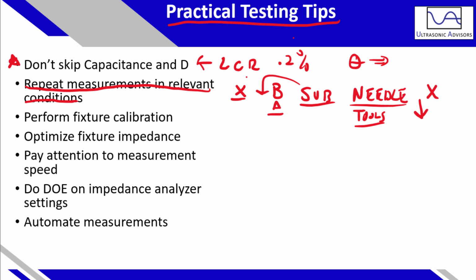And this kind of goes to the final point. Let me jump here, because it may seem like there are so many measurements to do. There are, and it's going to be a lot of handwriting unless you automate those measurements. I don't recommend skipping steps here, because a common occurrence in ultrasonic transducer development is that we encounter an issue, we want to look backward, but we were missing data. So if you automate measurements, you spend time taking more measurements. If that's not possible, spending more time on it will save you time in the future.